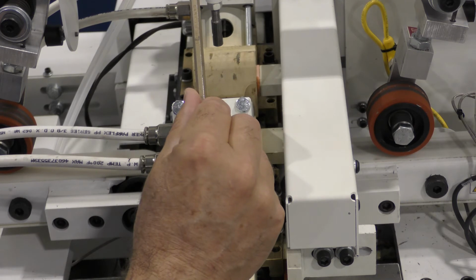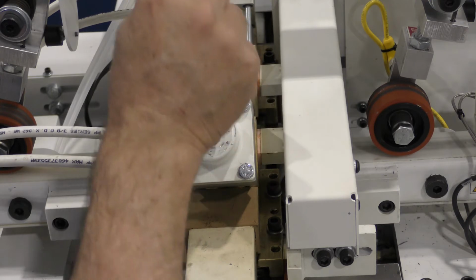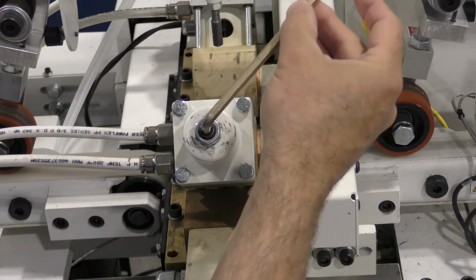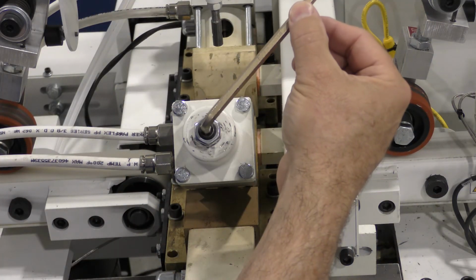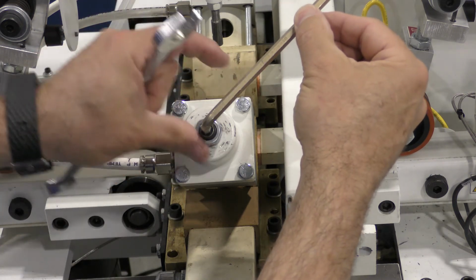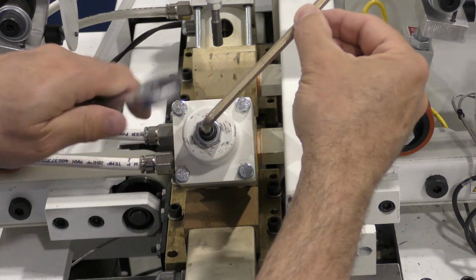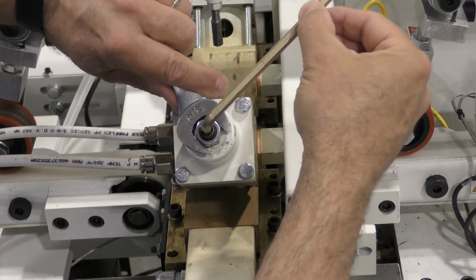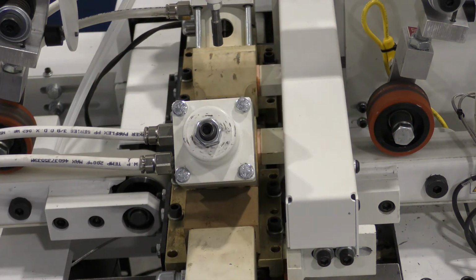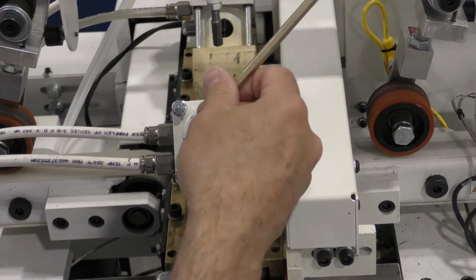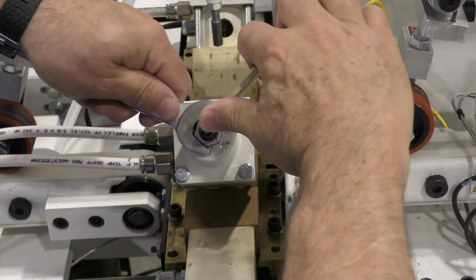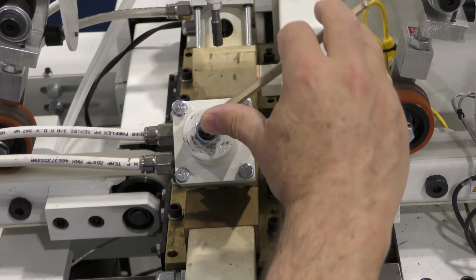If the heads are already in service and open less than 3 turns, then set them back to where they were. This will likely shorten the process of running this step if you only have a slight adjustment to make. If the heads have just been rebuilt, or if they were open more than 3 turns, then open the heads 1 1/4 turns.